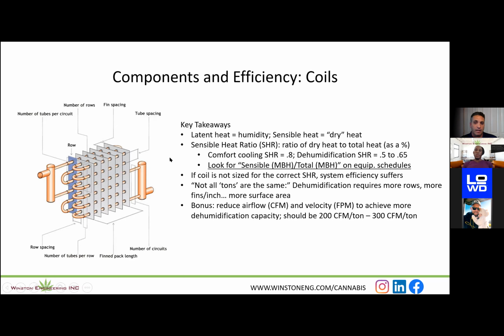There's a term in engineering and HVAC design called the sensible heat ratio. All that is the ratio of dry heat to total heat, okay? So if you're in your house or an office building, the sensible heat ratio on the air being served by the equipment is going to be about a 0.8 or a 0.9. So effectively 80 to 90% of the air in the space that equipment is serving is going to be dry heat. If you're looking more at one of these facilities, or a dehumidification application, again, the flower room, if you will, you're going to be looking at a sensible heat ratio of about 0.5 to upwards of about 0.65. So 50 to 65% of that air that the equipment is serving is going to be dry.